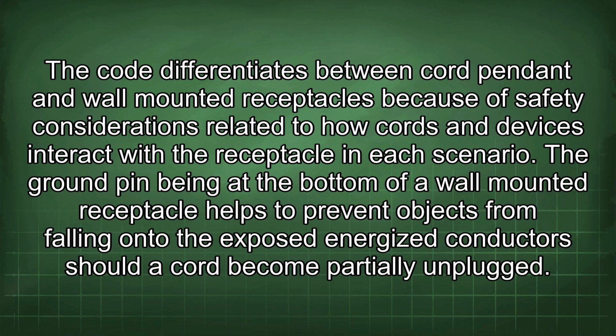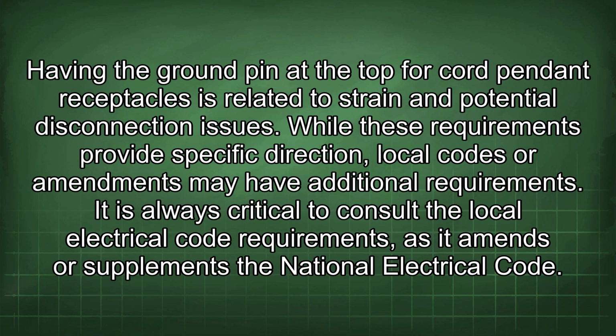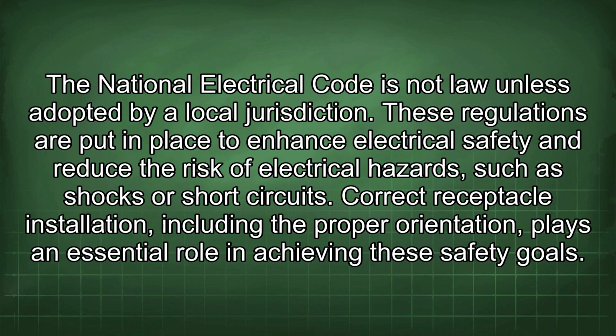The ground pin being at the bottom of a wall-mounted receptacle helps to prevent objects from falling onto the exposed energized conductors should a cord become partially unplugged. Having the ground pin at the top for cord pendant receptacles is related to strain and potential disconnection issues. While these requirements provide specific direction, local codes or amendments may have additional requirements. It is always critical to consult the local electrical code requirements as it amends or supplements the National Electrical Code. The National Electrical Code is not law unless adopted by a local jurisdiction.